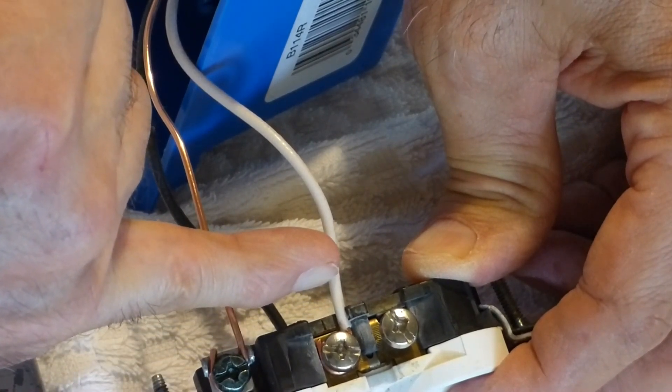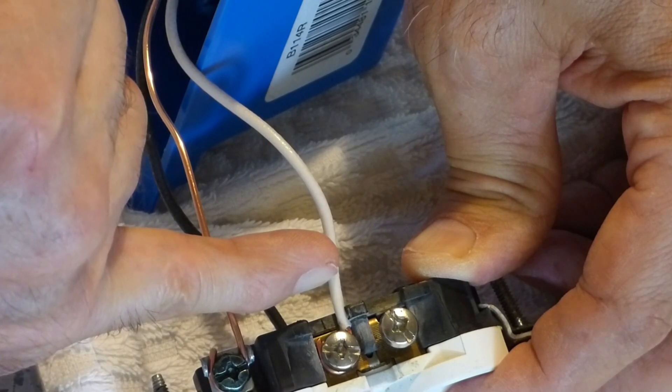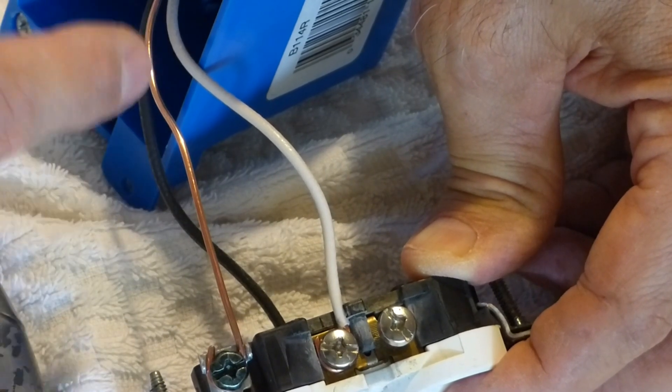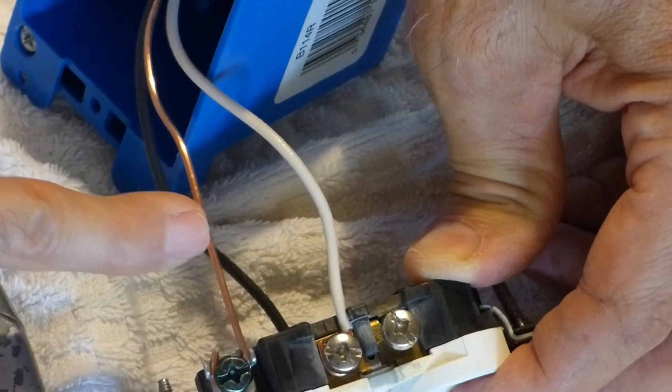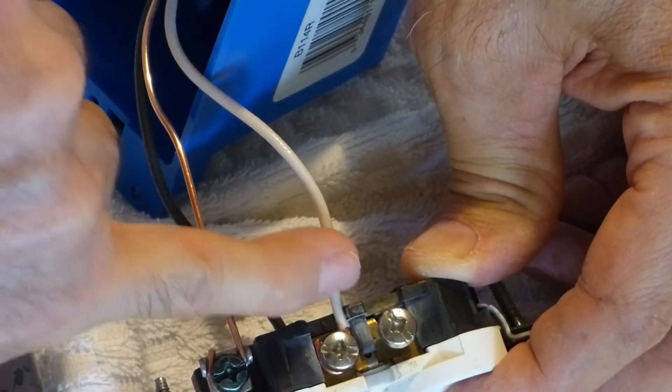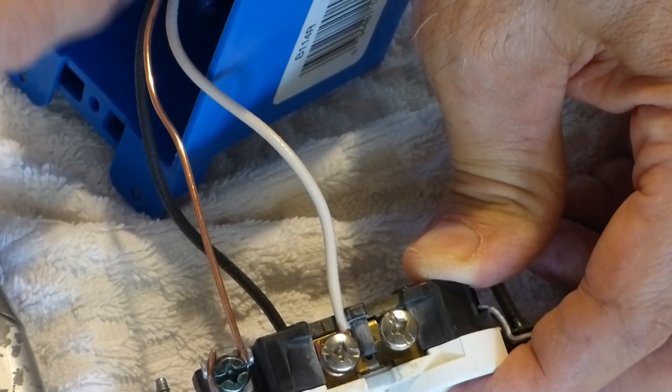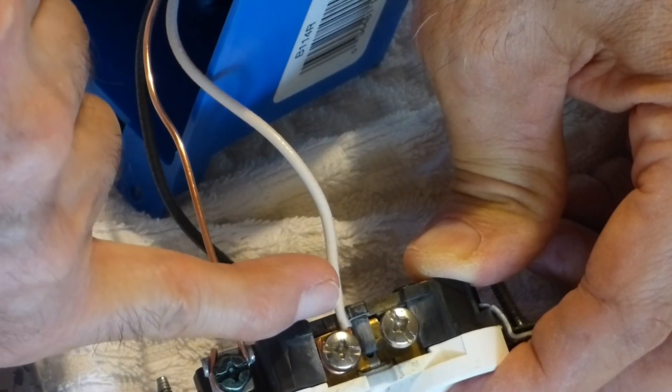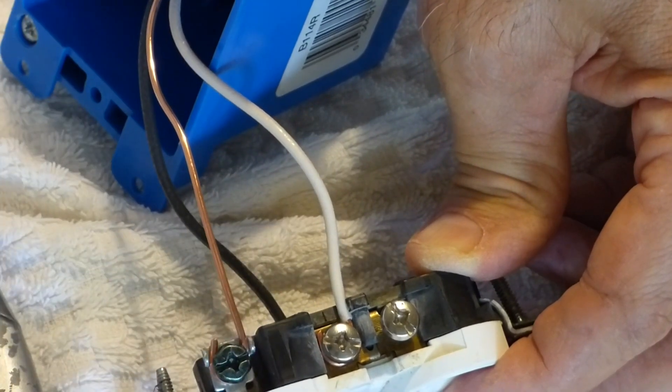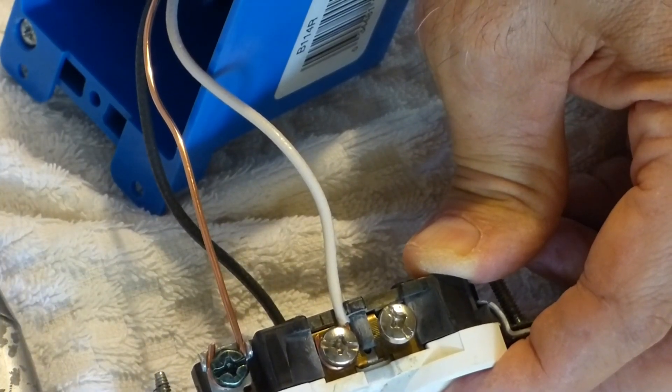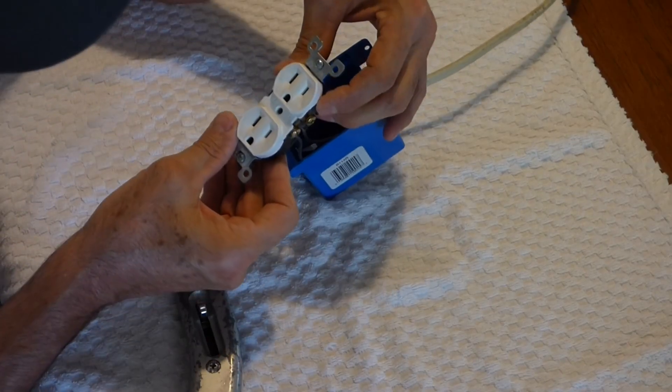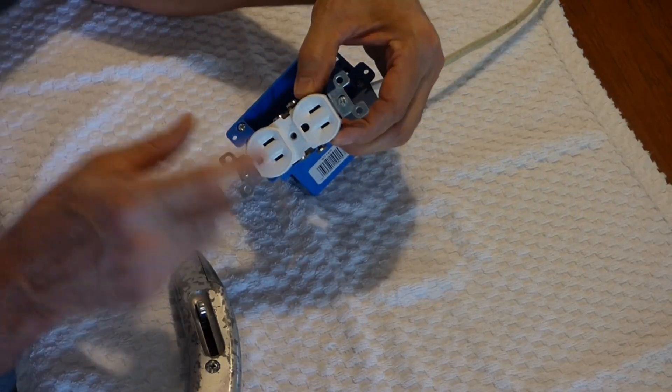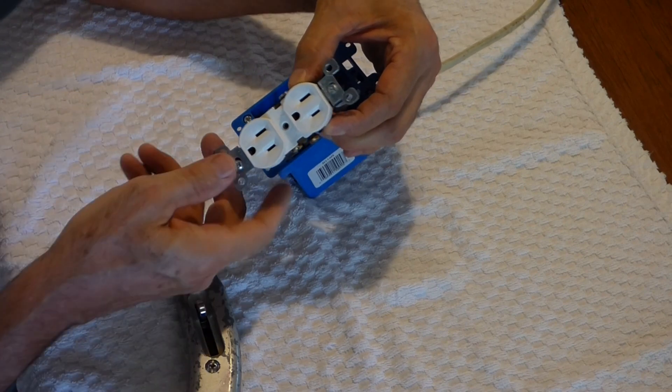If you get that strip down here and you've got bare wire showing here, it's possible when you tuck that wire in that this ground wire could touch that wire. Or if you have a metal box, that wire could be touched, and you're going to create problems with your receptacle.